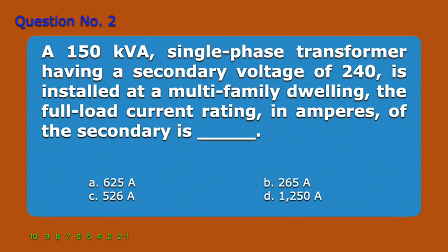Question number 2. A 150 kVA single-phase transformer having a secondary voltage of 240 is installed at a multifamily dwelling. The full load current rating, in amperes, of the secondary is blank. A. 625 amperes. B. 265 amperes. C. 526 amperes. D. 1250 amperes.